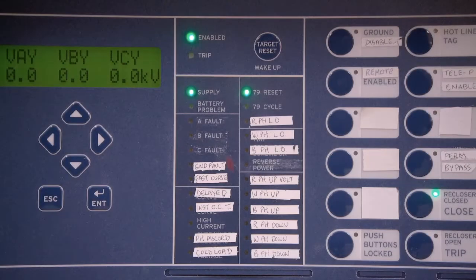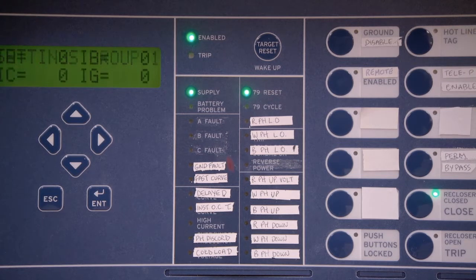On the top of this unit is the green Enabled indicator. This indicates that the recloser is set up and enabled for automatic recloses. The trip indicator will turn red when the unit has been tripped out, manually or otherwise. The supply indicator will remain green as long as an AC supply is present. The battery problem indicator will turn red should a battery problem occur. The batteries are automatically tested every 24 hours.